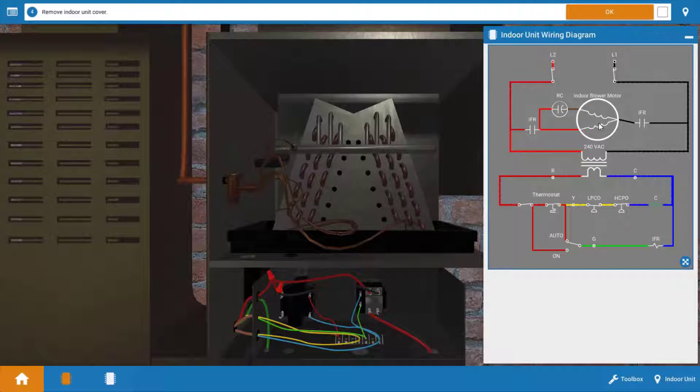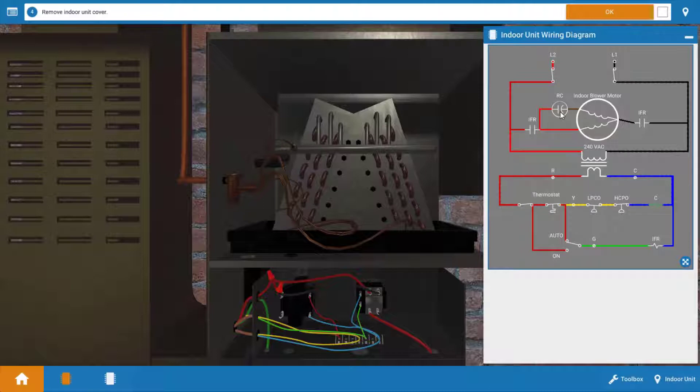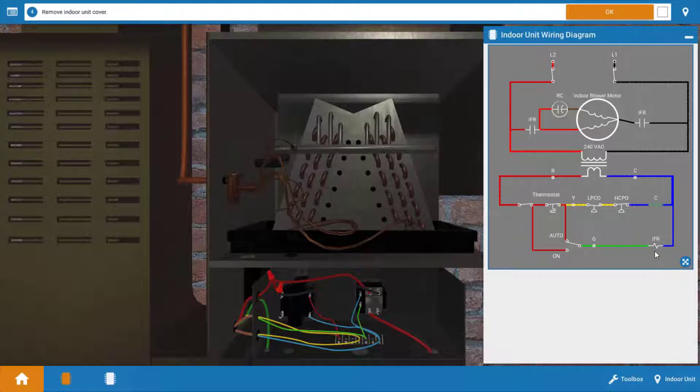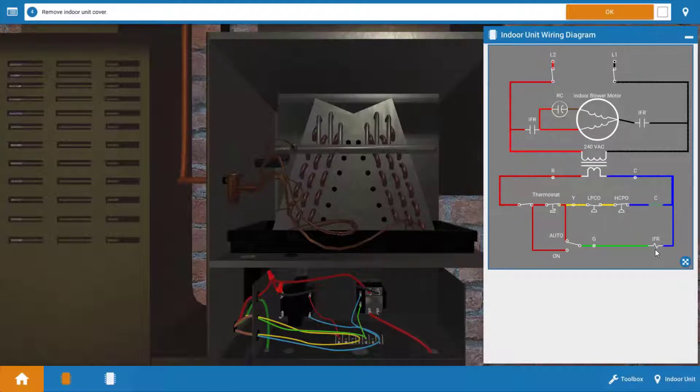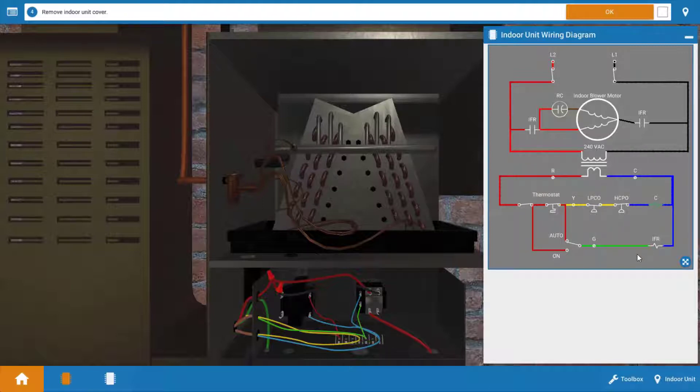It possibly could be a bad capacitor on the indoor blower motor. And it also could be the relay here, the indoor fan relay contacts, which are shown here and the relay coil that controls those contacts down at the bottom. The last possible component would be the fan switch within the thermostat.